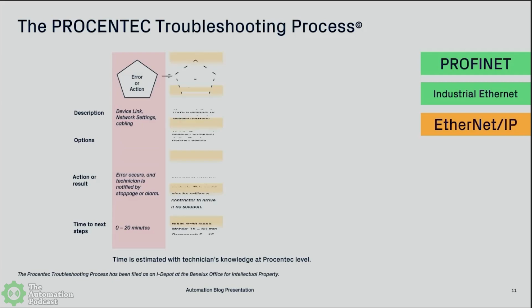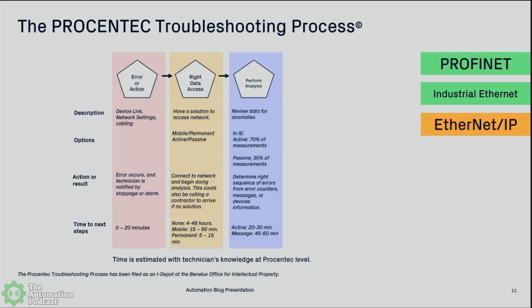So now the field technician has to access the right data. In general, what we say is you have a combination of mobile and permanent - this is under options - and you can also access the data actively or passively. Our field technicians have also spoken to the field technicians at facilities, and they say in general, if you have a mobile solution, it's typically 15 to 60 minutes for you to get out into the field, plug in, and start to get data that's relevant to identify. If you have a permanent solution, it's typically 5 to 15 minutes. The 5 minutes is finding the right network, logging into the device, say an IP address, and then beginning to perform the analysis.